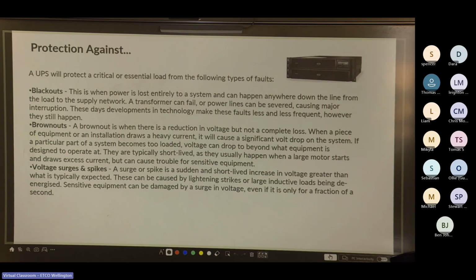And voltage surges and spikes. A surge or spike is a sudden and short-lived increase in voltage, greater than was typically expected. These can be caused by lightning strikes or large inductive loads being de-energized, so backfeeding from motors, and sensitive equipment can be damaged by a surge in voltage, even if it's only for a fraction of a second. So you'd also use surge protection to protect against this. But if you've got small motors, and there's a spike in voltage while it's being run, it can burn out the windings just because the windings are so small.